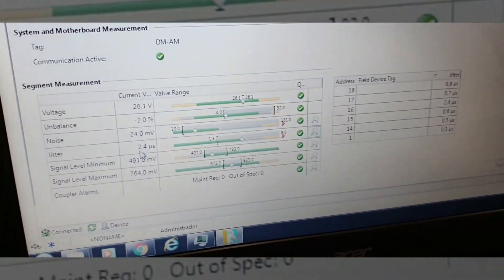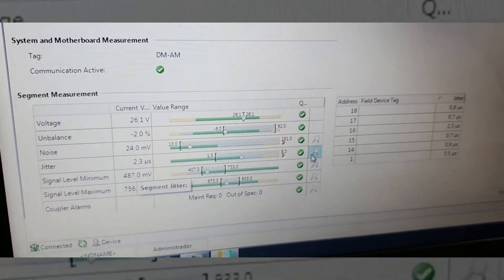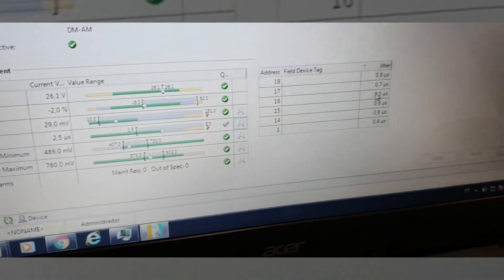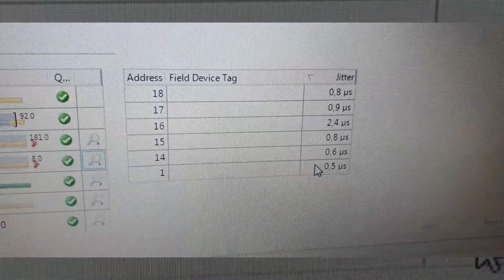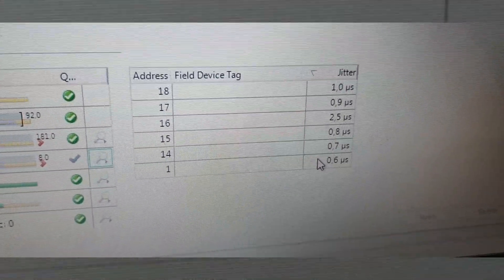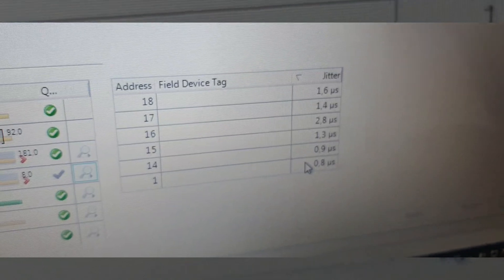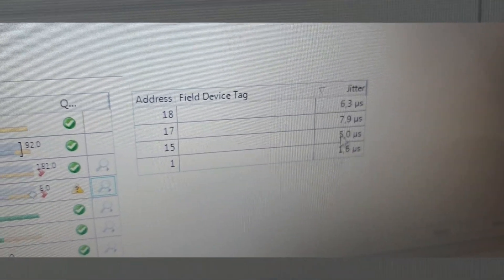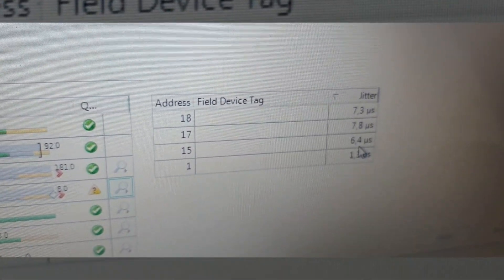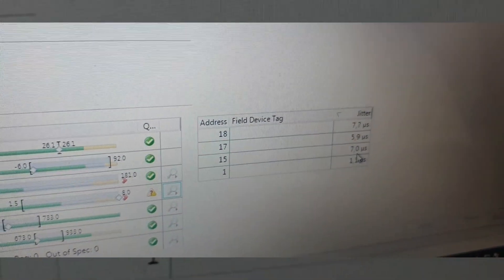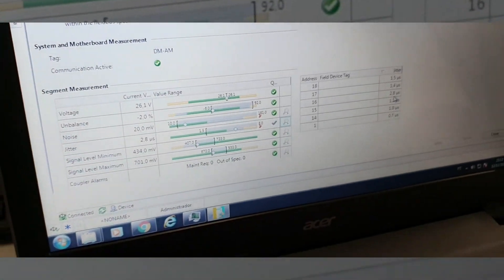Let's see jitter now. Jefferson is going to input a jitter fail into our network. Look at the jitter of the instruments — as he increases the jitter, you can see it increasing from each instrument. As soon as the jitter gets too high, look at the problem it inserts into our network. How important it is to analyze the network!